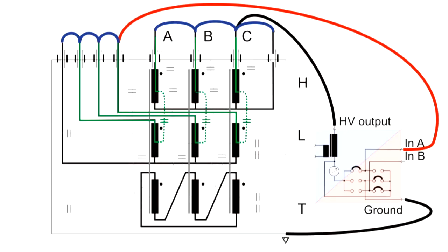If all bushings are connected to each other during a test, we only measure the dielectric losses. Now let's see what happens if we remove this connection. A capacitive current flows through the high-voltage winding and the low-voltage winding.